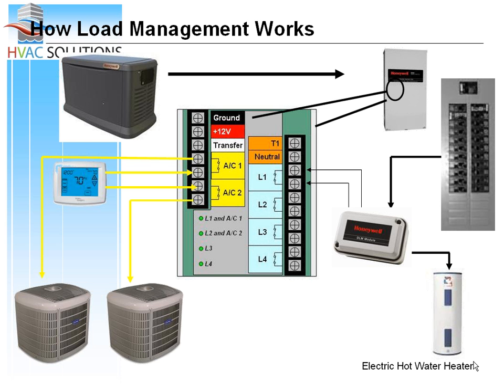One other thing we can do, if for some reason they said, I don't want that well pump to ever shed. I always want my well pump. Okay, we leave it on the 115 side. We don't shed it. What's the penalty? At that point, we have to size the generator for whatever we're leaving on the customer circuit breaker panel.